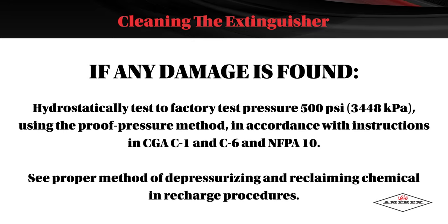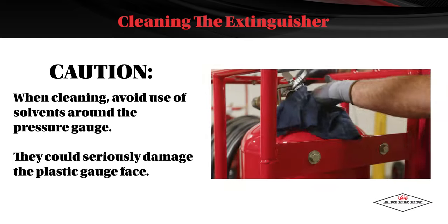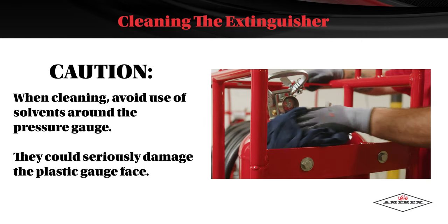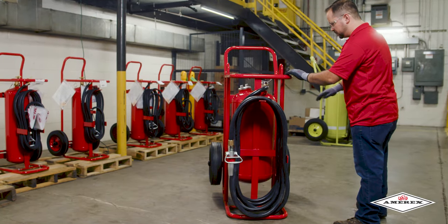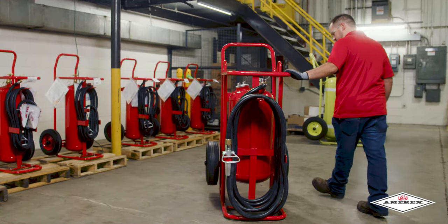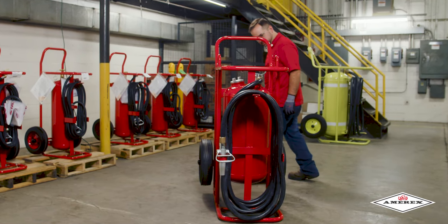See proper method of depressurizing and reclaiming chemical in recharge procedures. Caution: when cleaning, avoid the use of any solvents around the pressure gauge — they could seriously damage the plastic gauge face. Inspect the extinguisher for damaged, missing, or substitute parts. Only factory replacement parts are approved for use on AMEREX fire extinguishers.